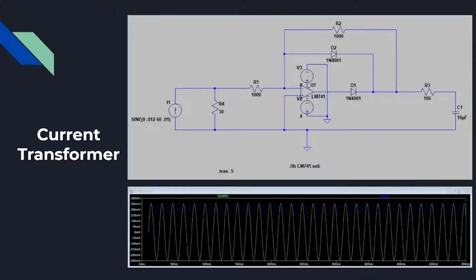There is also a moving average utilized in the software to guard against any transient spikes that may be caused by inductive or capacitive loads. This ensures that the breaker will not trip if there's a spike in current for a specified period of time. In software, there is a simple equation that reverses Ohm's law from the series resistor to give us the actual current value on the line.